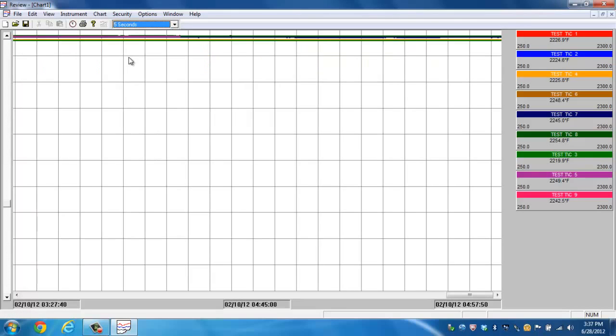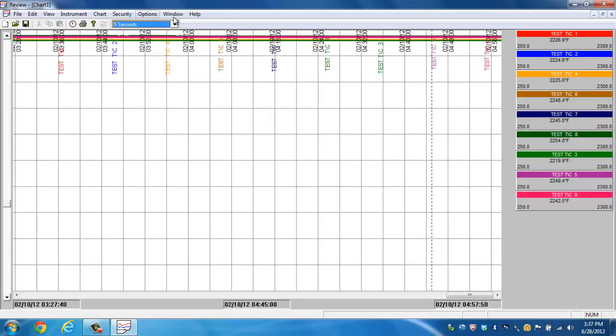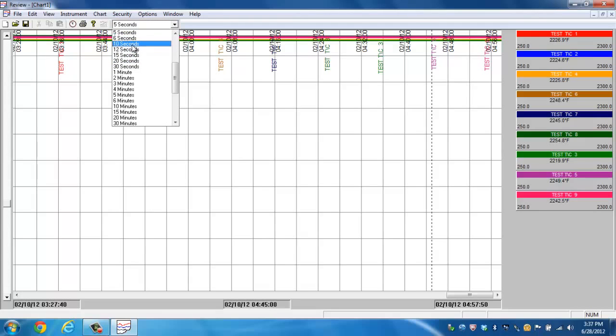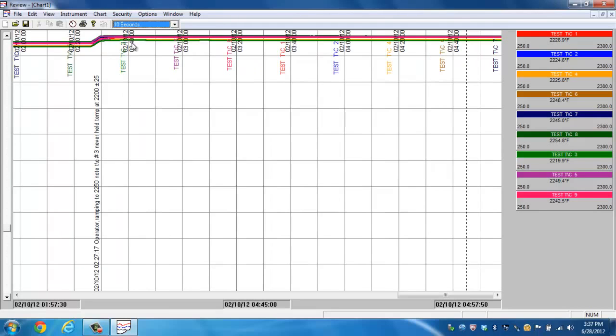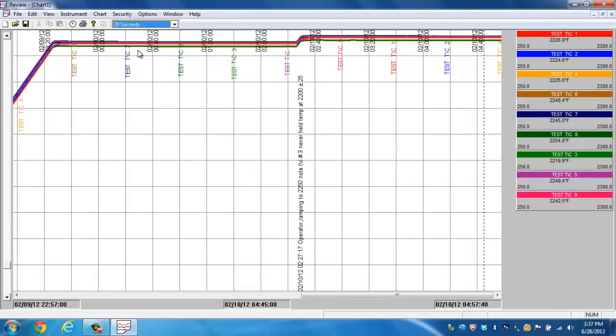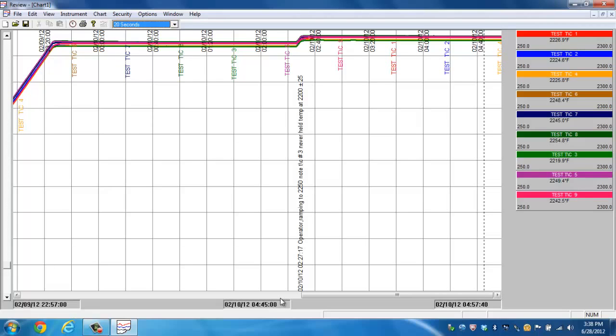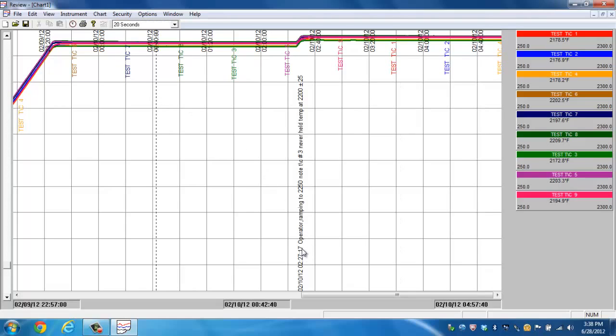Now granted, I'm looking at one-second intervals. If we want to see a bigger picture of what we've collected, let's move out to something more like five seconds. If we move it out to something like ten seconds, now we can start to see some type of variation in data. If we keep moving out just a little bit more, now it looks like we are doing some type of set point survey, possibly. Another thing I want to point out though, on the left-hand side here and on the right-hand side, we have some dates and times. That's also based on the furthest left and furthest right of the chart. So the chart that we're looking at goes anywhere from February 9th at almost 11 o'clock at night, all the way until the following day at 5 o'clock in the morning. So that's the basic chart operation that we're looking at. But what you see roughly in the middle of the screen, that would be one of the messages that we were talking about. That's optional for you to have that displayed or not. We chose to leave that on.